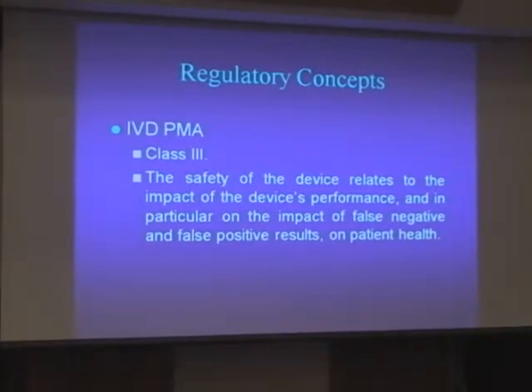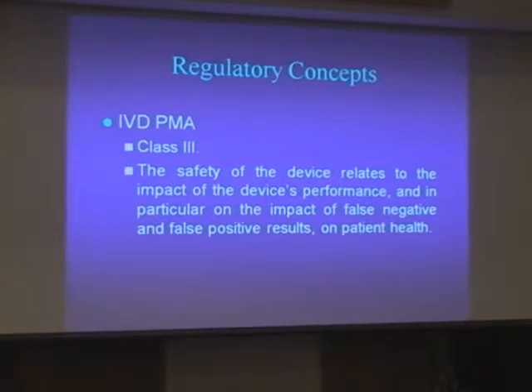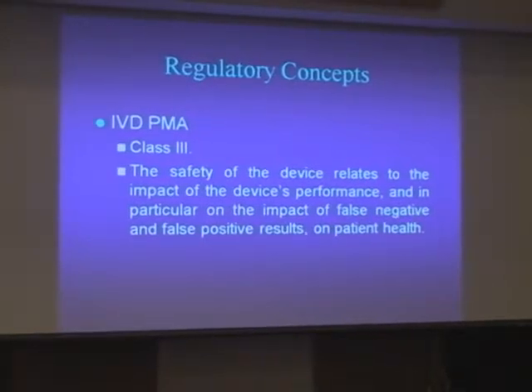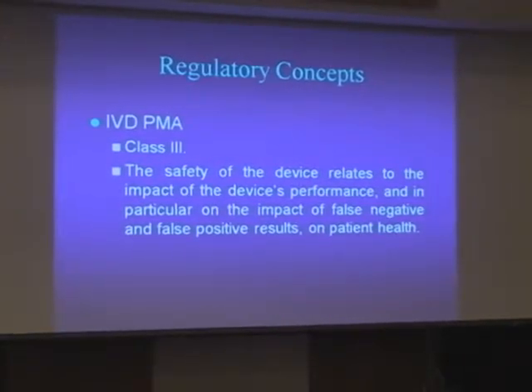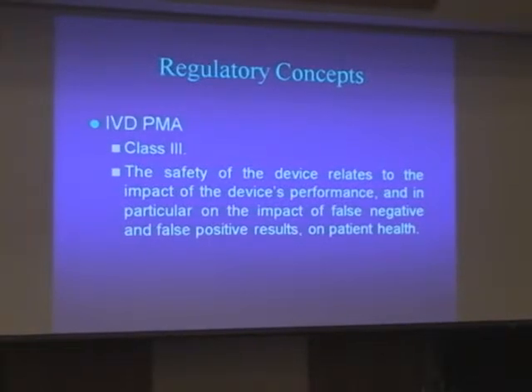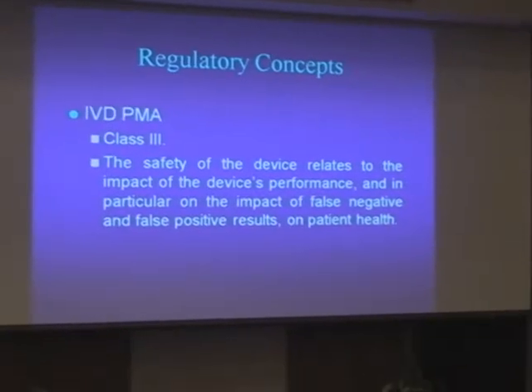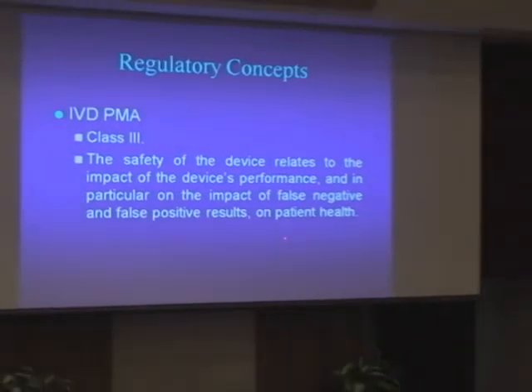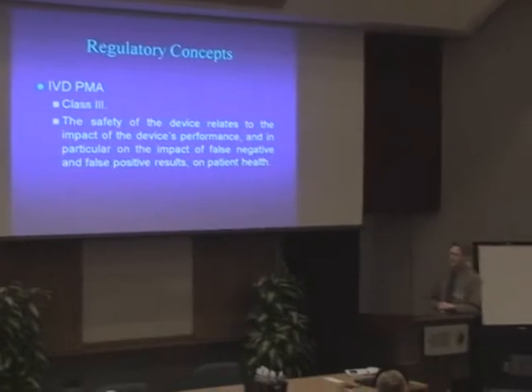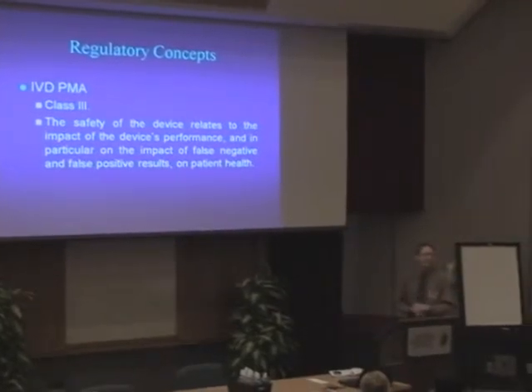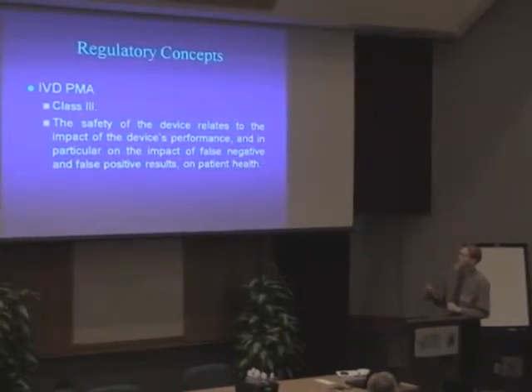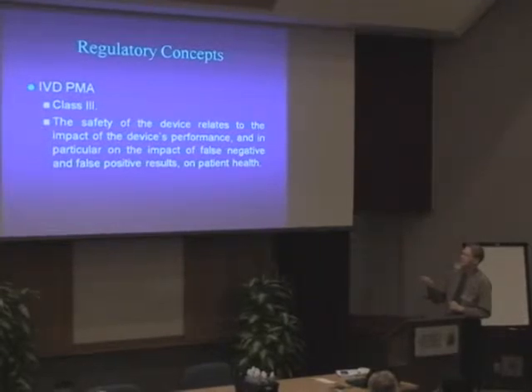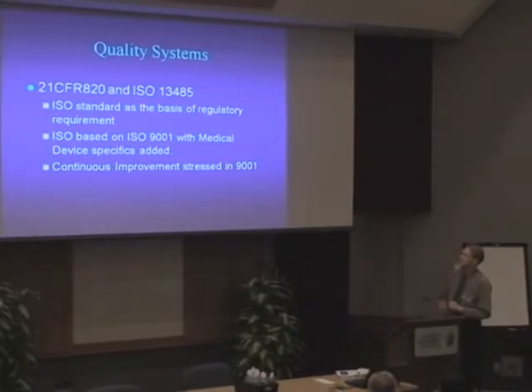For Class III, it again depends on the false negative and false positive results. The classification is risk-based. If there's a risk of a false negative or a false positive having a serious health implication, then that's something you're going to have to be concerned about, control, and have the data to support.